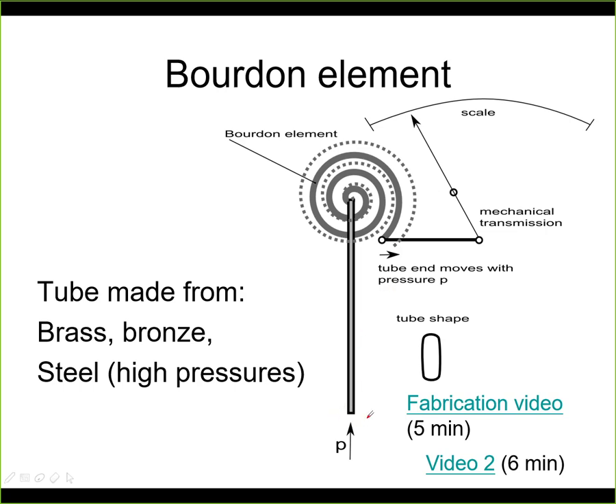On this end we have an opening to the Bourdon tube, so we can connect the pressure P that we want to measure. If this pressure P is increasing, this Bourdon tube is trying to straighten itself, so the end of the Bourdon tube is moving like this. This is the dotted spiral that we see here, and as this end is moving, this motion of the Bourdon tube is transferred through the levers to the scale, and we will see a change.